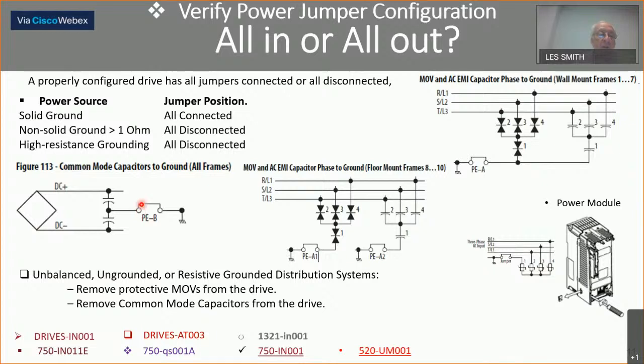PEB here, you see this jumper. These capacitors are actually the same capacitors for the bus charging. We just happen to have a jumper in the middle, and we take the ground and we use these to filter the noise that may be out there to ground. PEA, right here, these are the metal oxide varistors, MOV, and the capacitor filters out there.